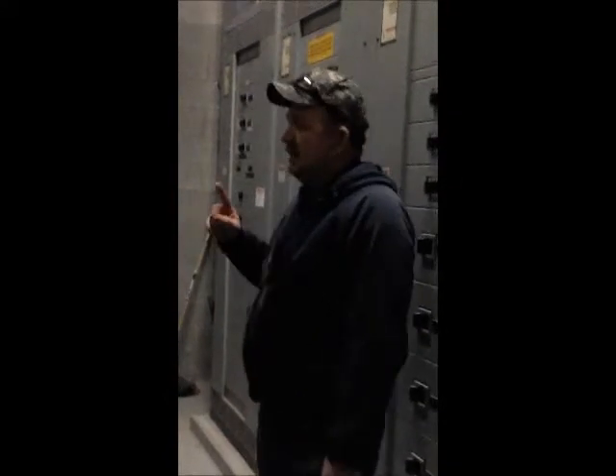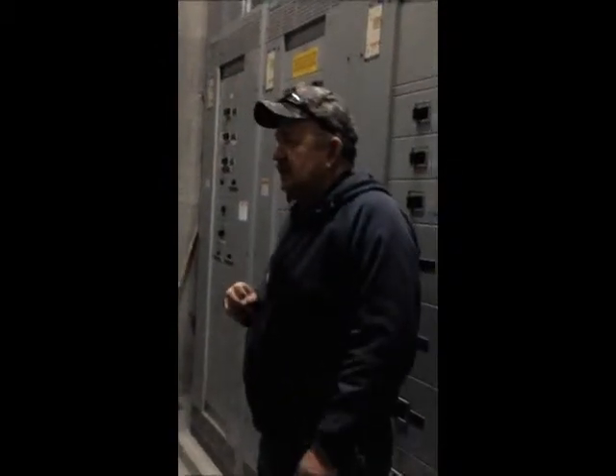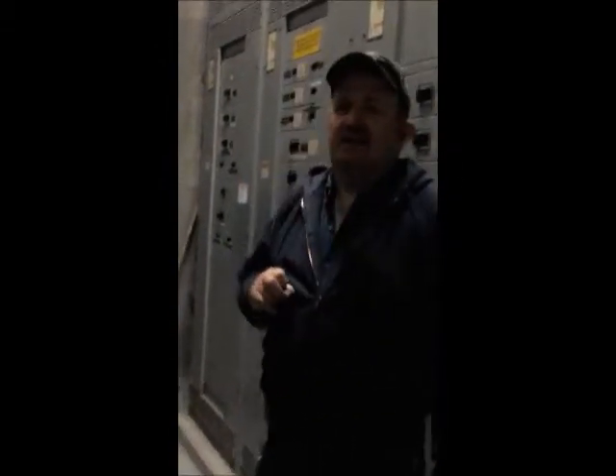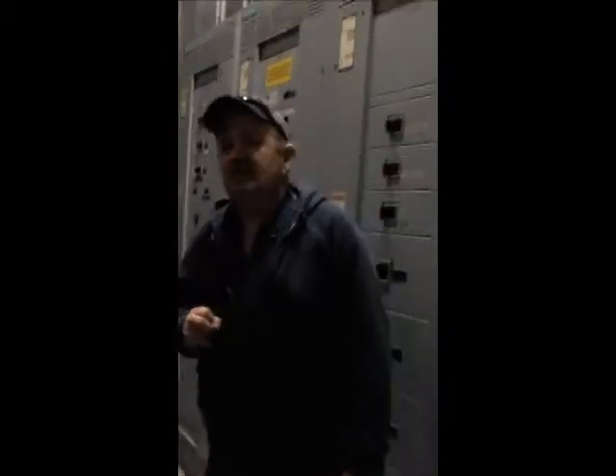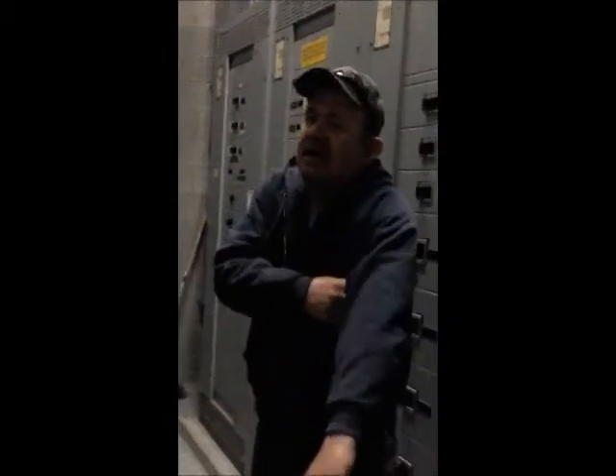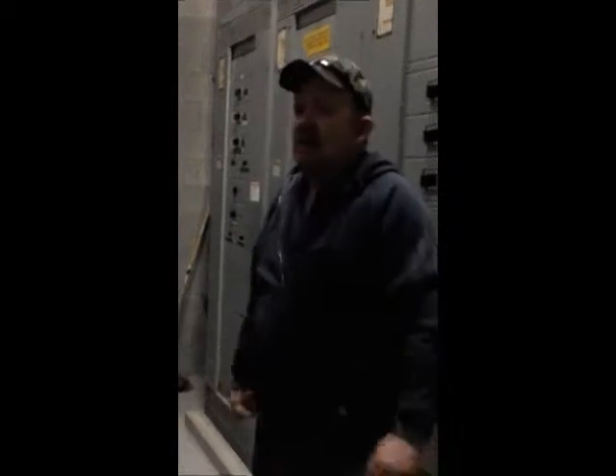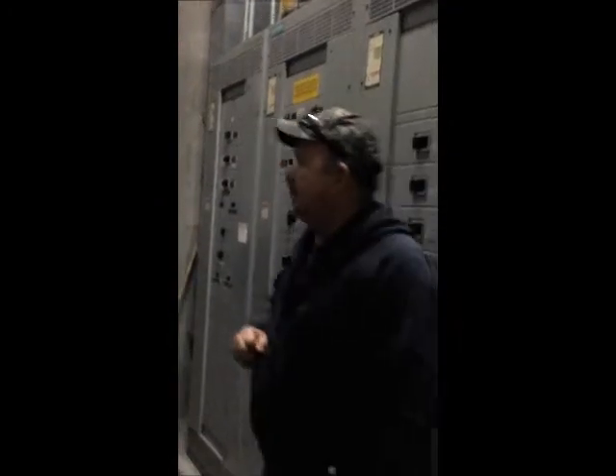The other thing is, you must make sure the rooftop units are shut off. The generators won't handle the rooftop units. The bigger generator, the 1 meg, might handle some of them, not all. When they're running the air conditioning rooftop units, you can run a couple, and that's about it.